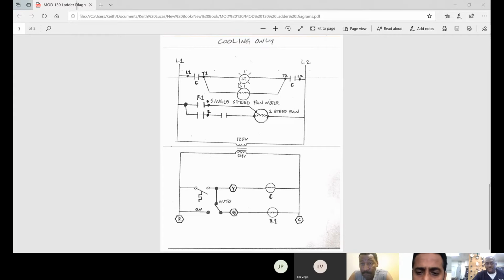Now we have T1 and T2 on our contactor. We have two things connected to T1 and T2: our green light, which is our fake compressor, and our single speed fan, which is our fake condenser fan. Notice we got two things connected to this little dot right here - one wire going to our light, the other wire going to our fan. Same thing happening on the other side to T2. So we got 4 wires to connect. Let's do that.